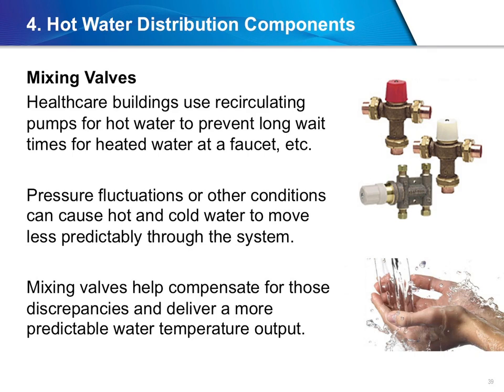However, things like pressure fluctuations can cause hot and cold water to move less predictably through the system, while valves in the system could malfunction or fail. Mixing valves help compensate for those discrepancies and deliver a more predictable water temperature output. Clearly, there is a need to meet both the needs of killing Legionella with higher temperature water and the human requirements of a lower safe temperature. The solution is found in the use of tempering valves or mixing valves that blend hot water with cold water in a controlled manner. This ensures constant, safe outlet temperatures while minimizing the occurrences of both scalding and Legionella.